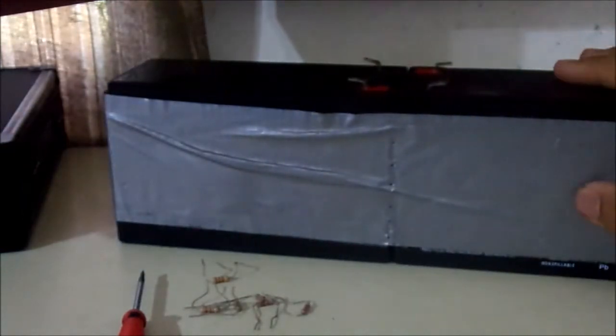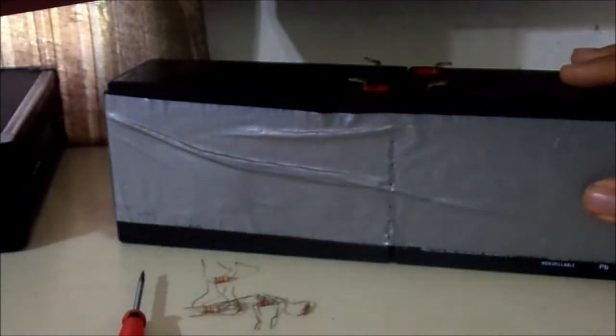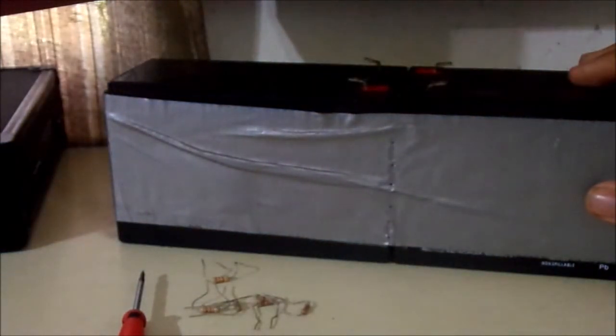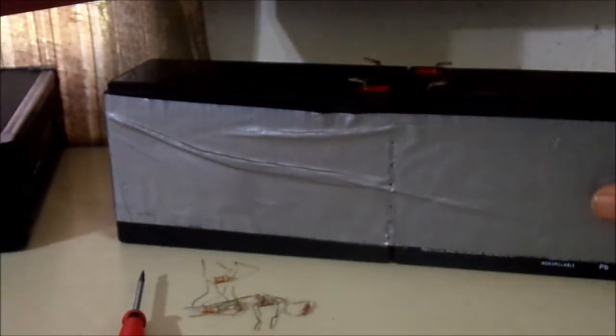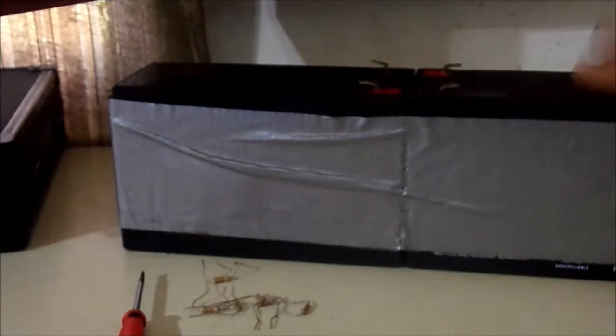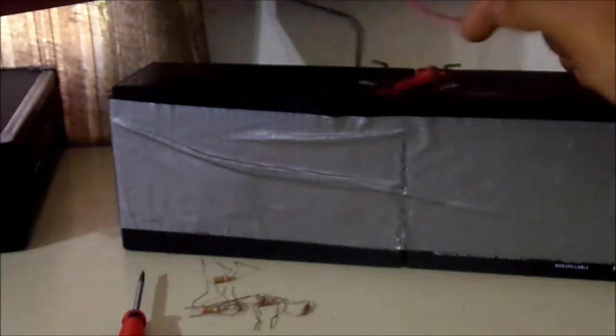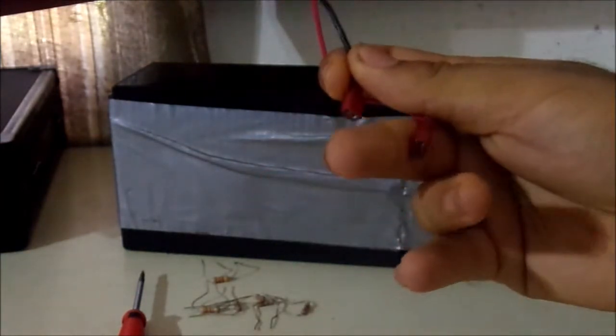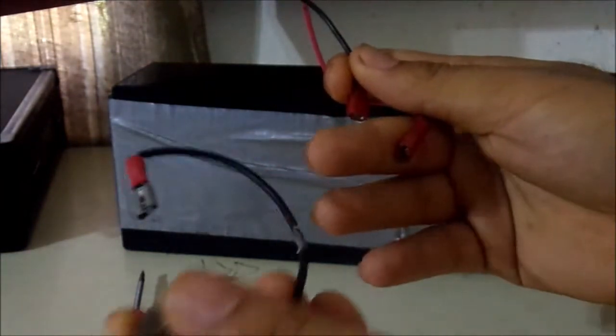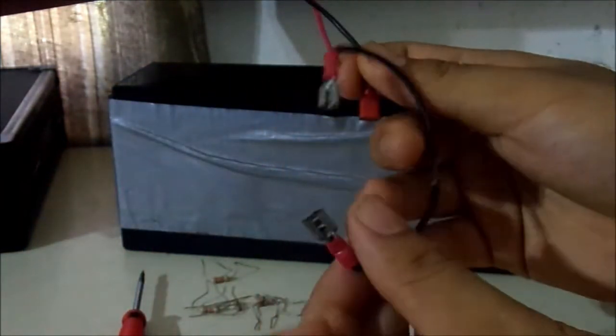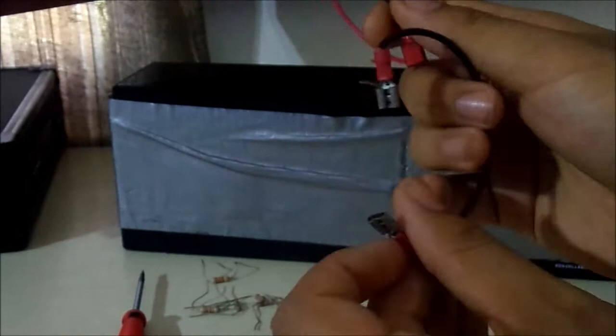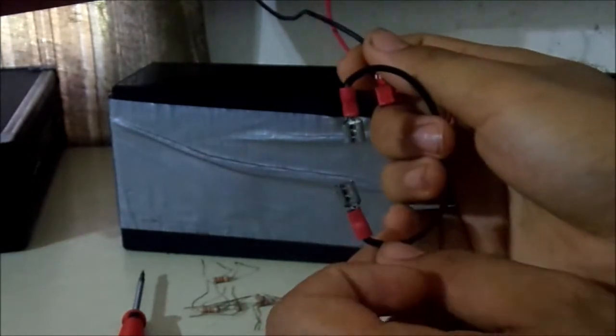What's up next is that you need two 12 volts, 7 amp sealed lead acid battery. So this is the battery you will need to hook up to your fire alarm control panel. The fire alarm control panel should come up with these. I will show you later on how to wire it.